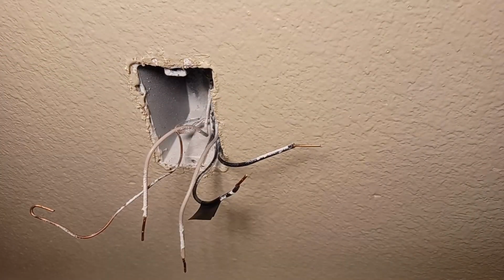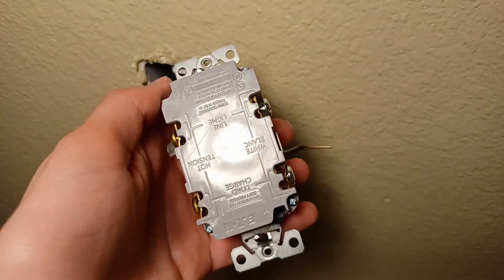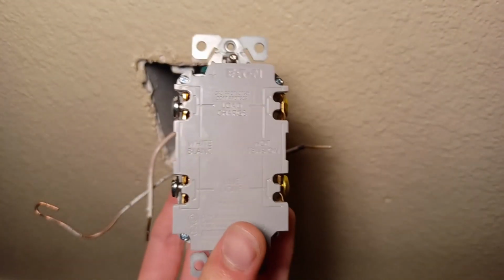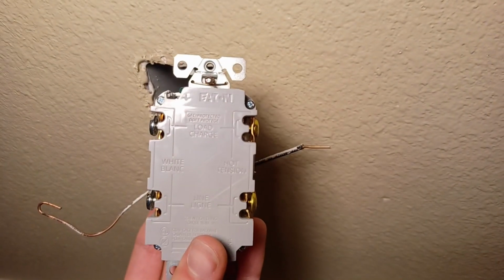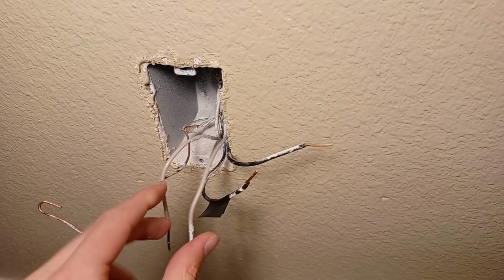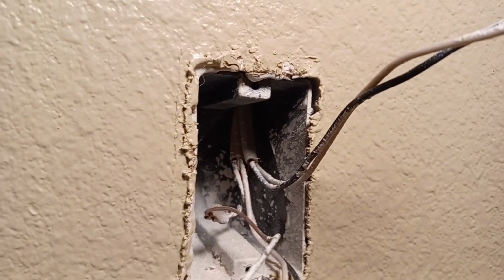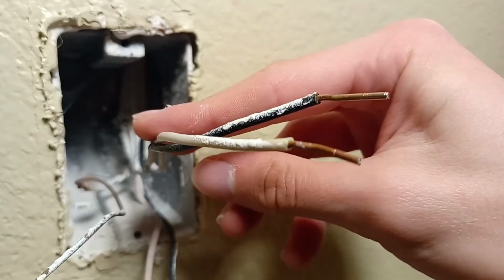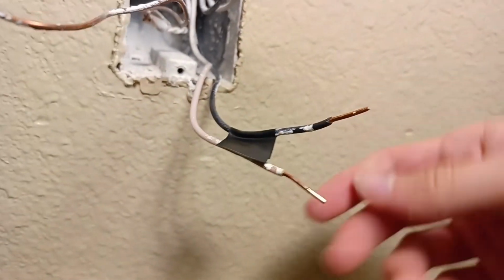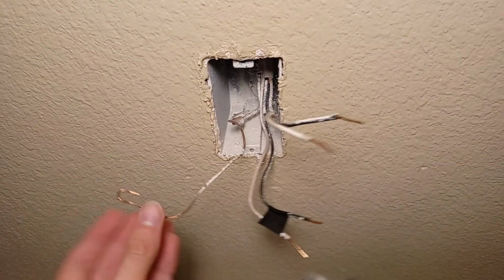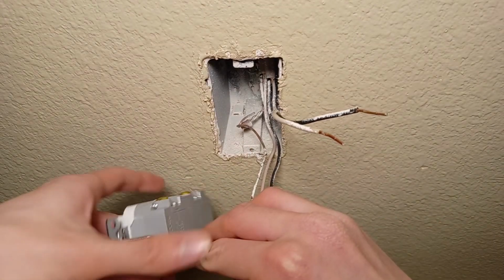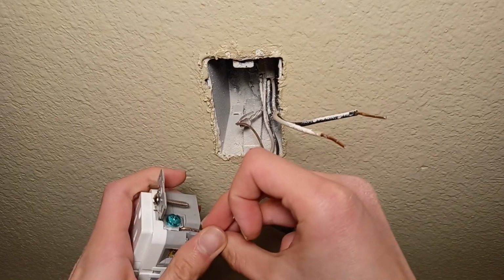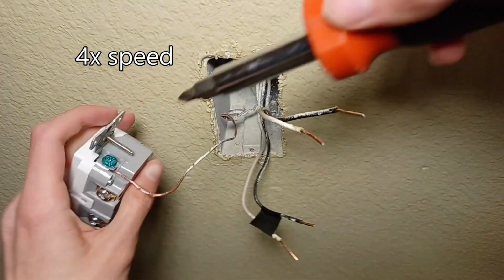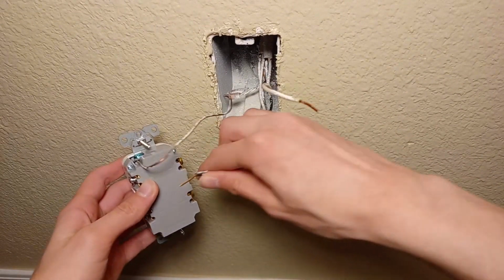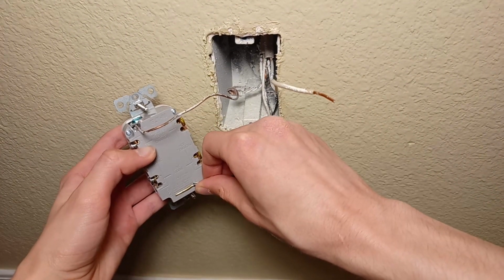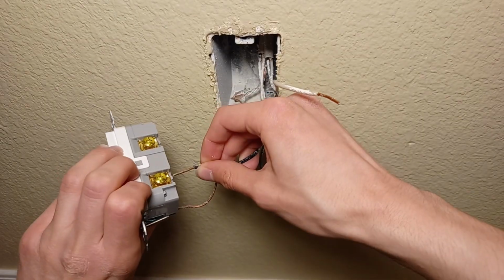Now, for the GFCI, both the hot and neutral must be connected through it on the appropriate line and load terminals. So let's find which cable belongs to the load. This top cable seems to be the load because that's what I did not mark. And this bottom cable is the line because that's what I marked. Now the ground can be connected to the green grounding terminal. Now the load wires, this label shows how long the wire should be stripped, which this one matches.